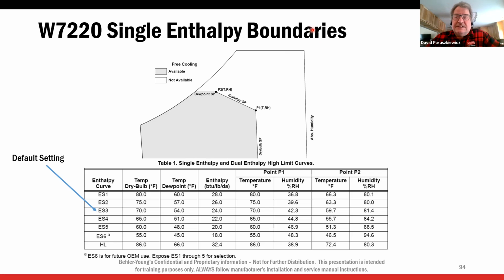Now this is a little different now because we're no longer looking at enthalpy. We are now looking at temperature and humidity separately. The factory default of that control is the ES3. We don't have A, B, C, D, E anymore. So enthalpy setting 3 is the default, and it actually is a range. Instead of one single point, it's a range.